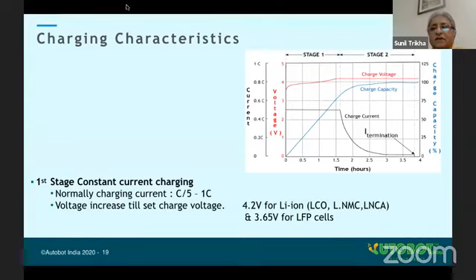After reaching 4.2 volts, it changes to constant potential voltage, where the voltage is maintained at 4.2 volts. When you float, the current starts coming down, because the differential between the charging voltage and the battery EMF becomes very small. These batteries are not floated for all the time, not kept on float for days together. So there is another cutoff: once current comes down to C/40, meaning for a 100Ah battery when current comes to around 2 to 3 amps, the charging is terminated.